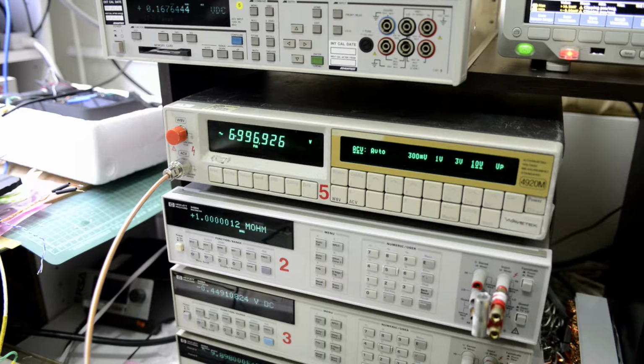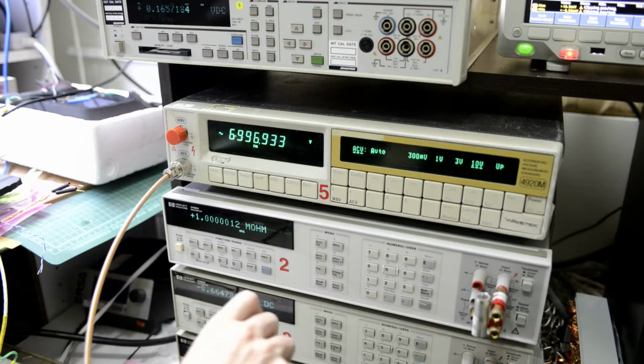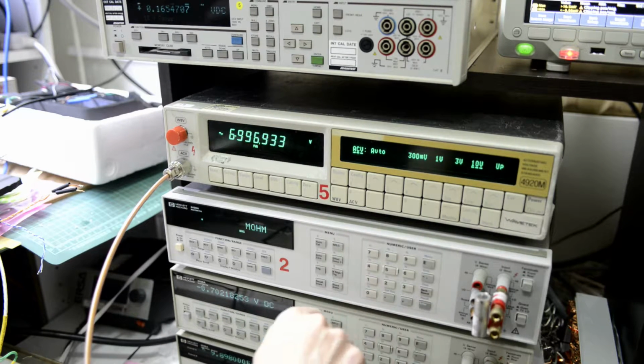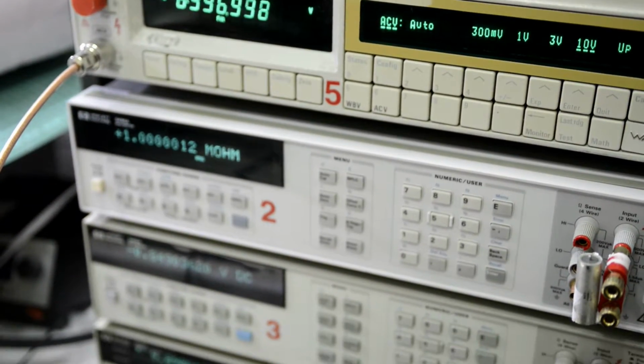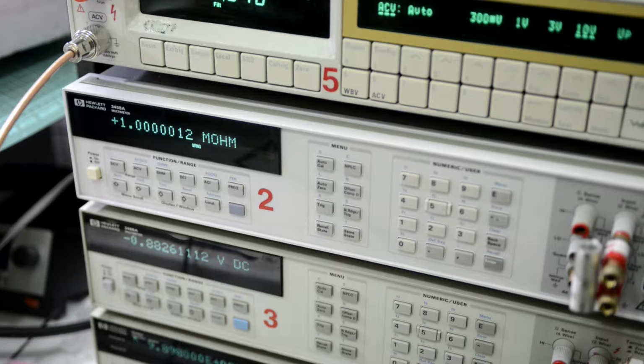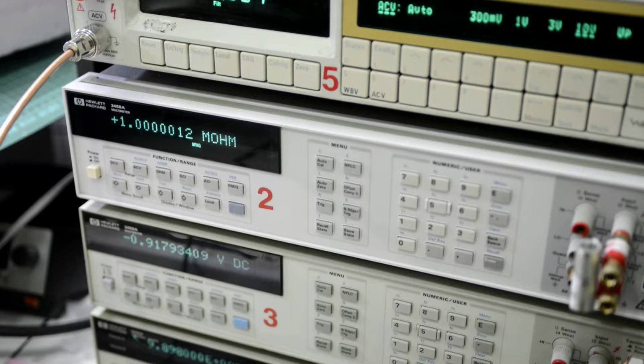We're back to measuring the 1 mega ohm resistor. So I'll just write down the values for each range on the HP meter, and then we can compare on the same values on the Advantest meter. And I use NPLC 100 and autozero enabled, and offset compensation is disabled. There we go. Should be nice and clear.